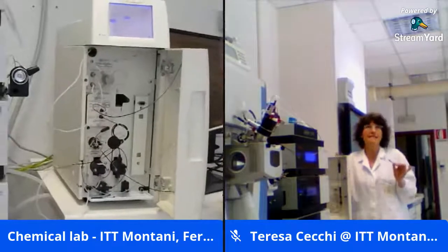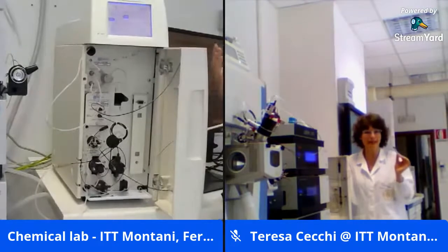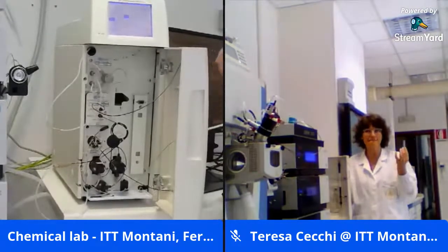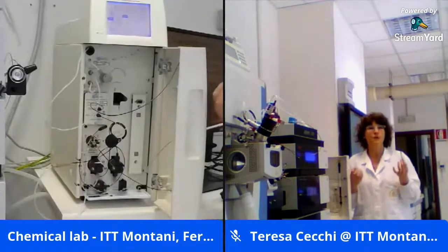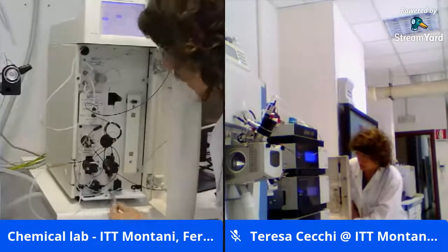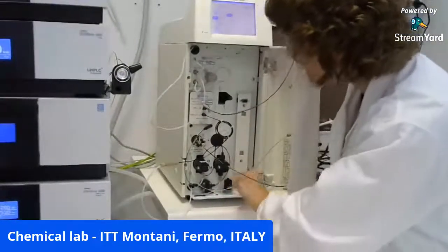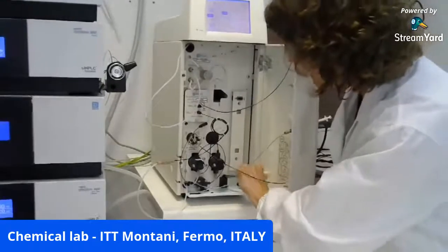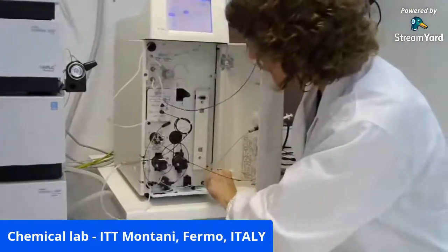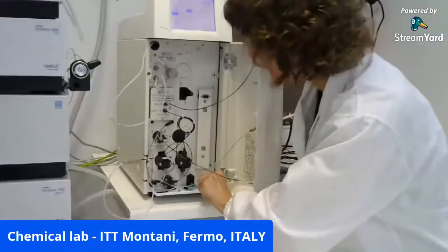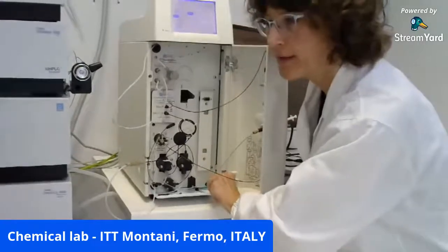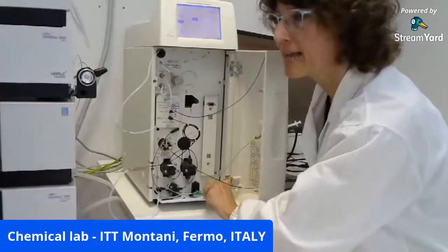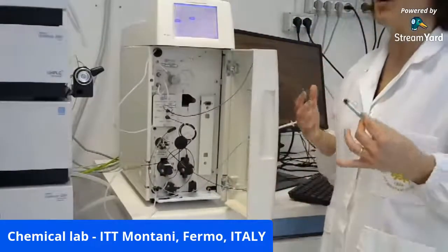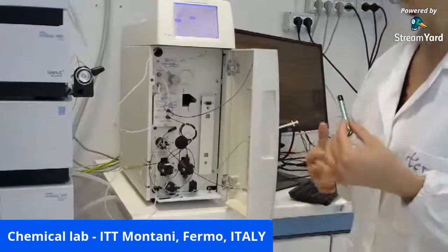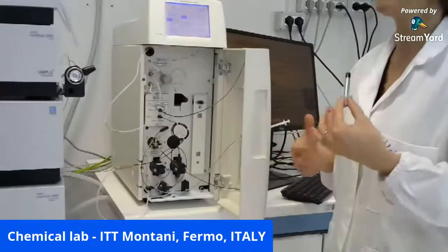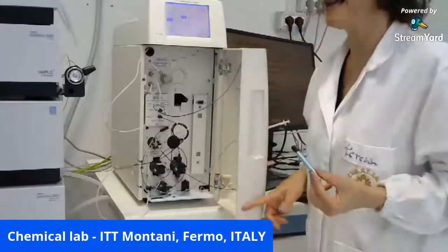A very small leakage, let's say, for example, one drop per minute or something like that, would not be detected as a massive decrease in the pressure. For this reason, the drops would get inside a small vessel here. Here you find a conductivity meter. If the vessel is full with the eluent drops, the conductivity meter would touch the liquid and would alert us that there's a small leakage. The constant flow is very important to have reproducibility. So the system would alert us again.